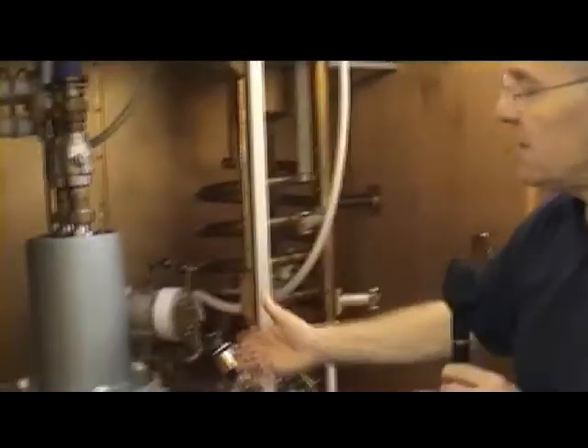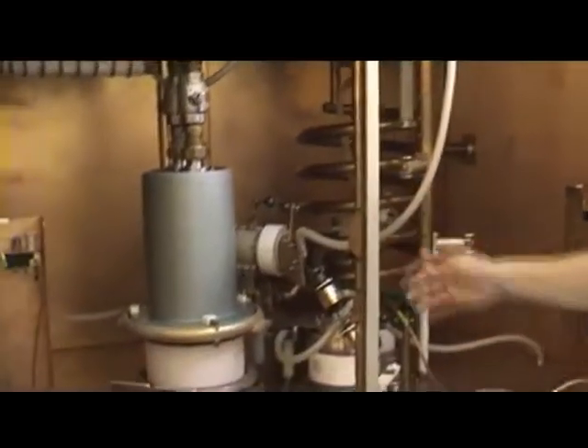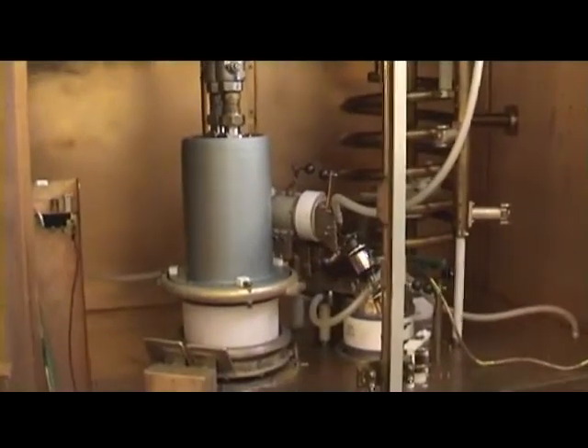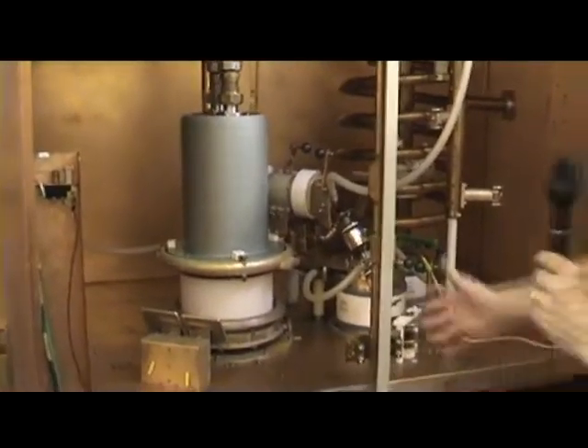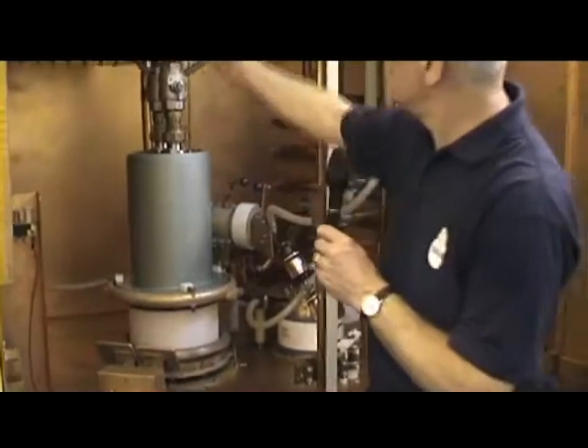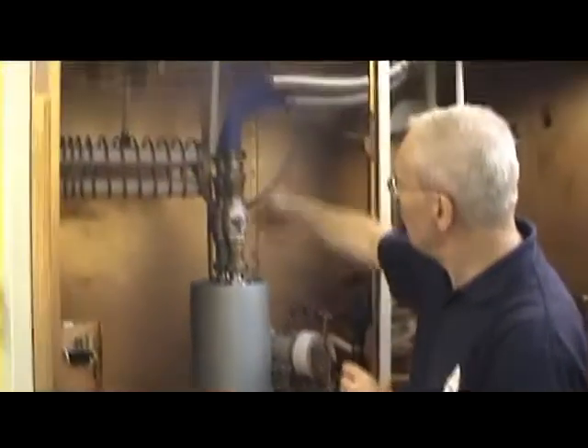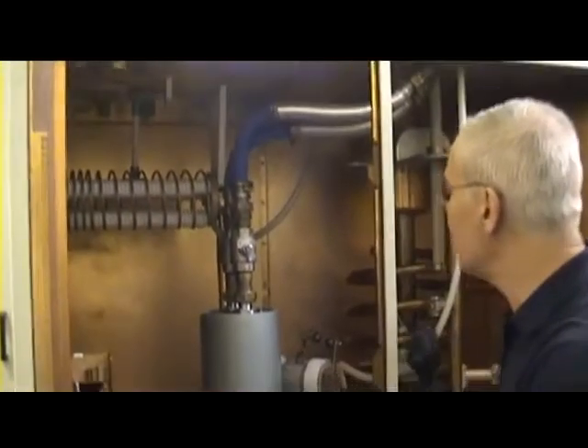Right, here we are in the rear of sender 92 with the doors open looking at the RF section. Single tube in these transmitters. It's a 500 kilowatt Thales tube. Again hypervapotron. Considerable water supply through there.